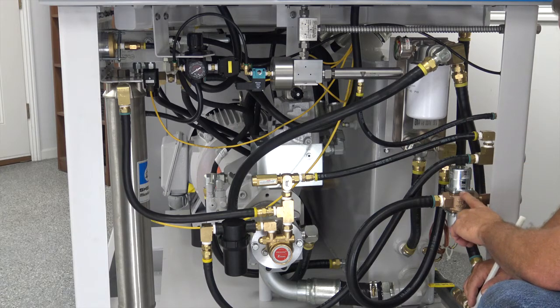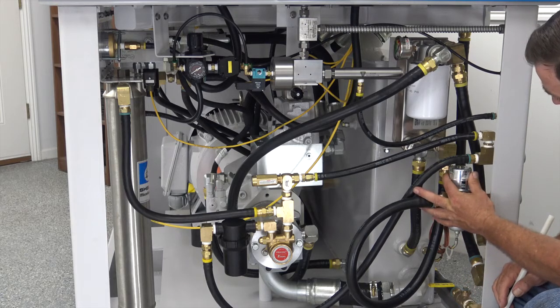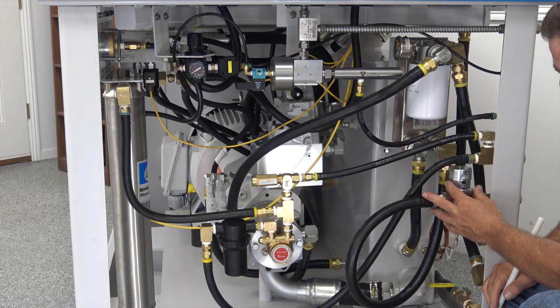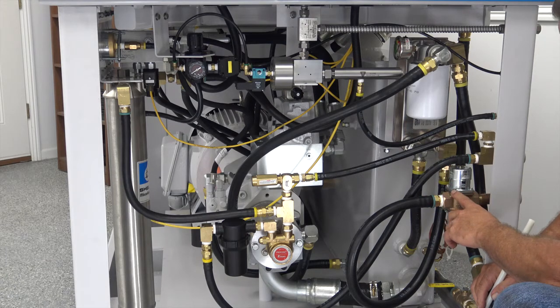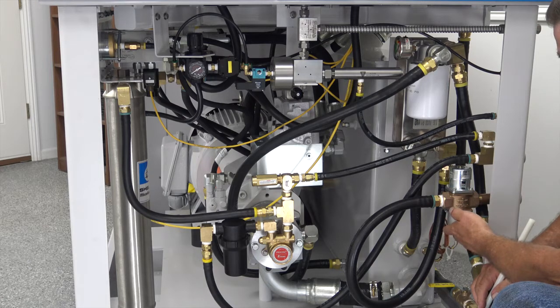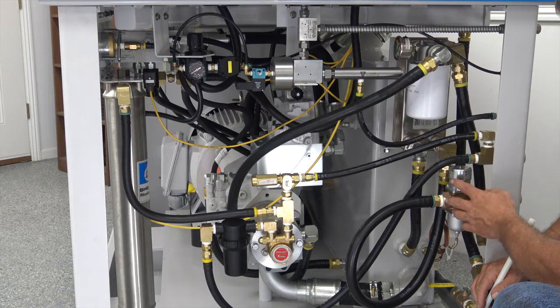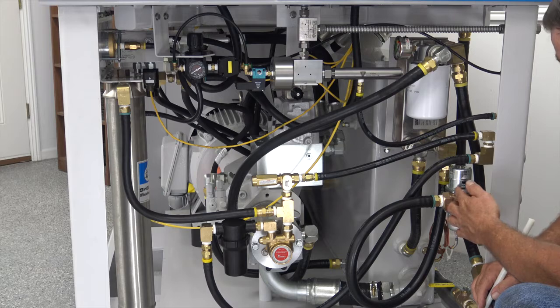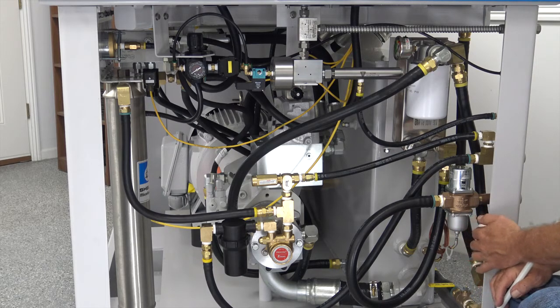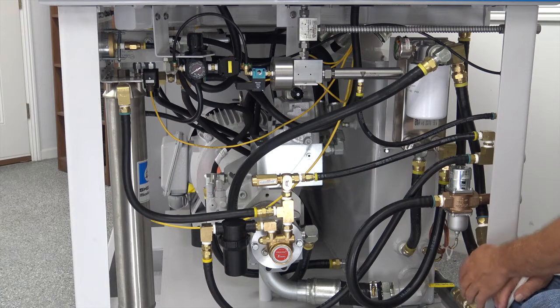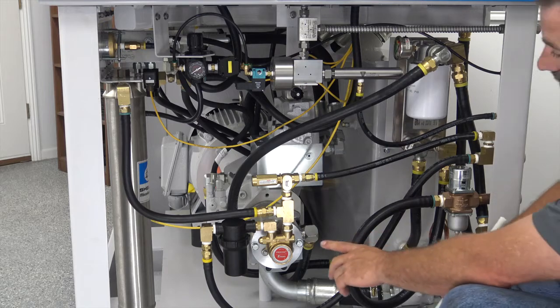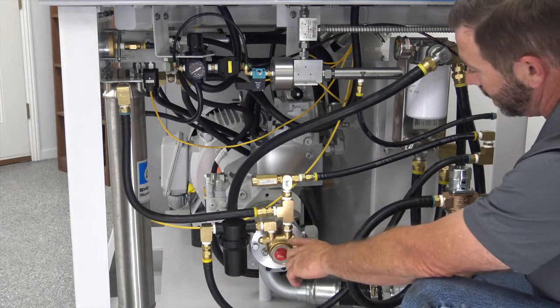You have the mechanical water valve here. You can adjust it by turning the top of it clockwise or counterclockwise. That's how you increase or decrease the temperature of this machine. The more you turn it clockwise, the more pressure it takes from the thermocouple to open the valve, therefore increasing the temperature of the unit. Of course, that works just the opposite by turning it counterclockwise. Going on further down, you have the cooling water, cutting water outs, and of course your drain for your hydraulic reservoir on the bottom. If we work back across the unit, this is your booster pump.